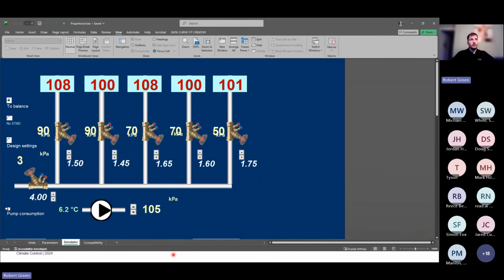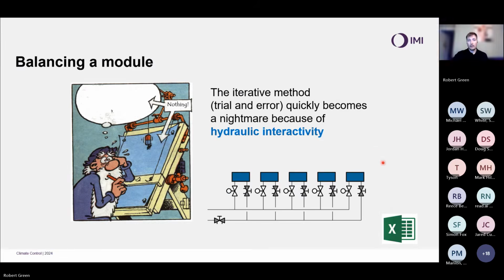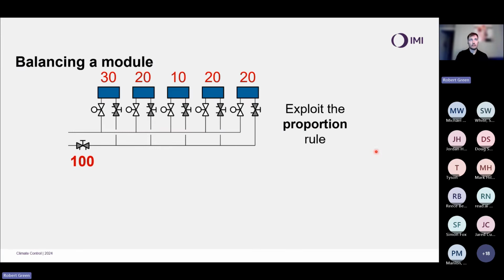In terms of consumption, this is running currently at 180% of the optimized setting. So i.e. when we are using nearly twice the pumping energy we need to get the flow to the right area on this pretty simple system. And what we're going to look at now is something called the proportional rule. Now, the proportional rule is a really important thing with manual balancing.